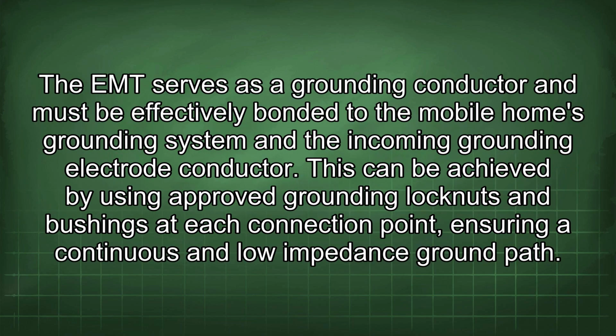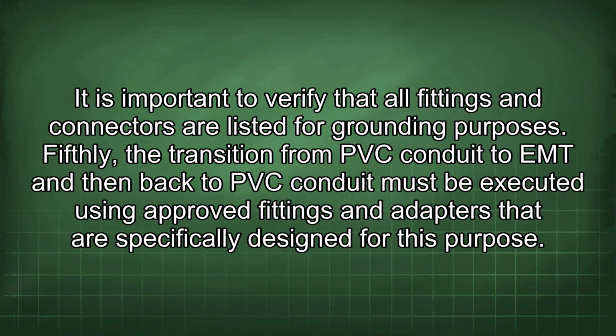The EMT serves as a grounding conductor and must be effectively bonded to the mobile home's grounding system and the incoming grounding electrode conductor. This can be achieved by using approved grounding lock nuts and bushings at each connection point, ensuring a continuous and low-impedance ground path. It is important to verify that all fittings and connectors are listed for grounding purposes.